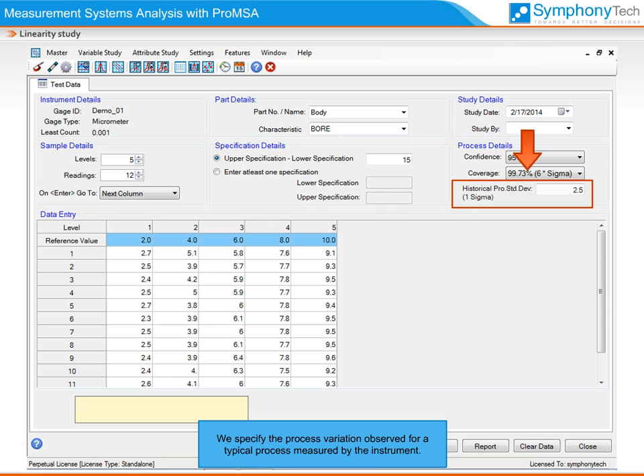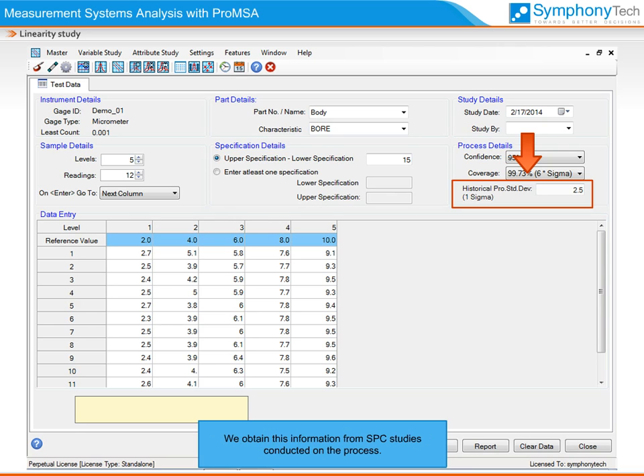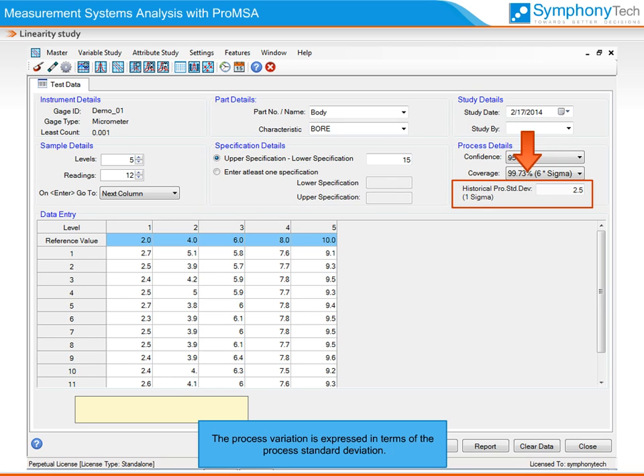We specify the process variation observed for a typical process measured by the instrument. We may want to use the most critical parameter the instrument measures for this purpose. We obtain this information from SPC studies conducted on the process. The process variation is expressed in terms of the process standard deviation.